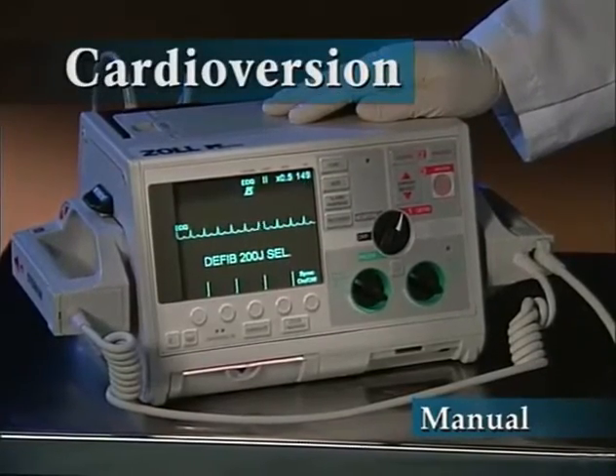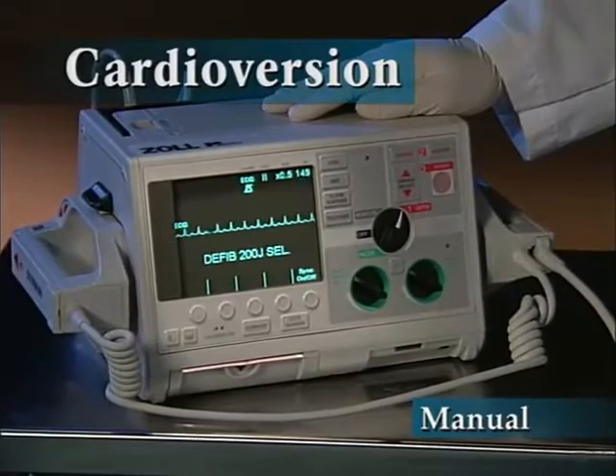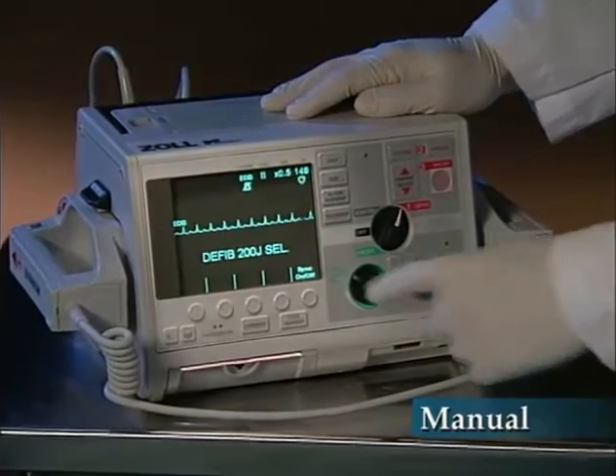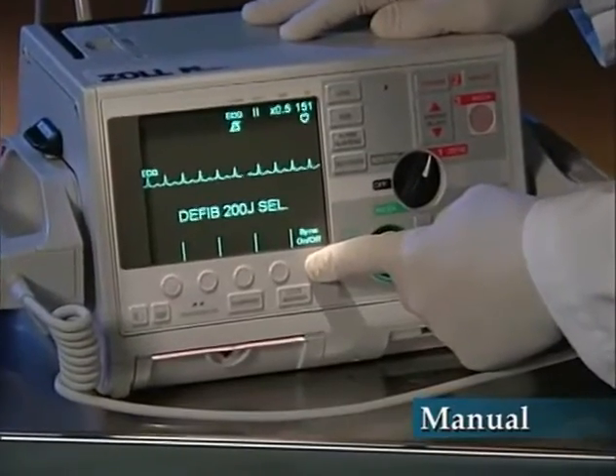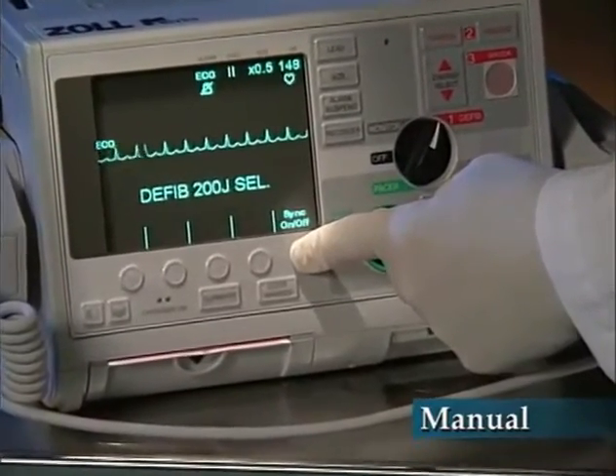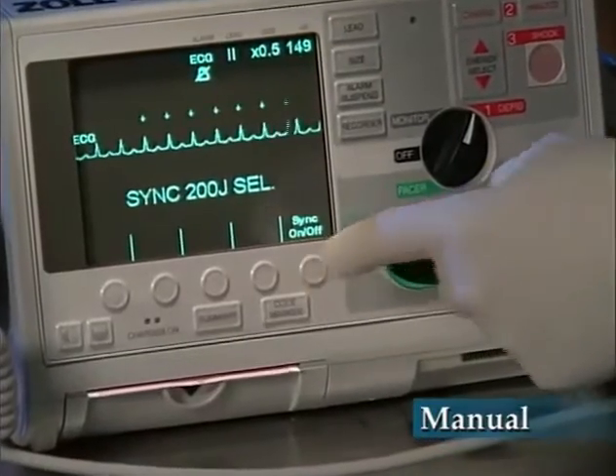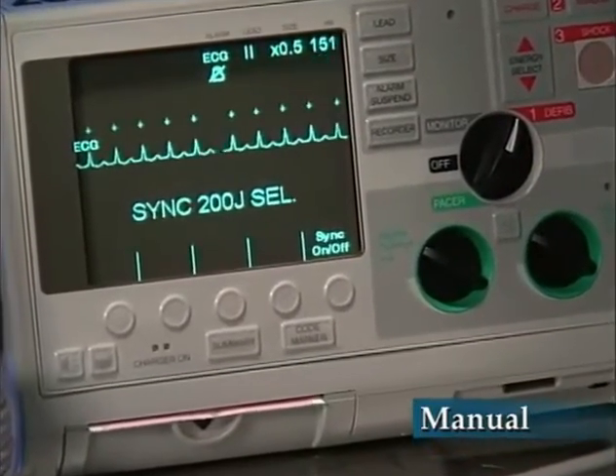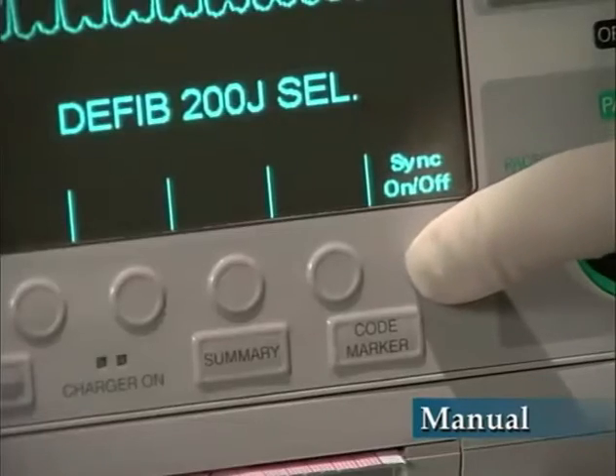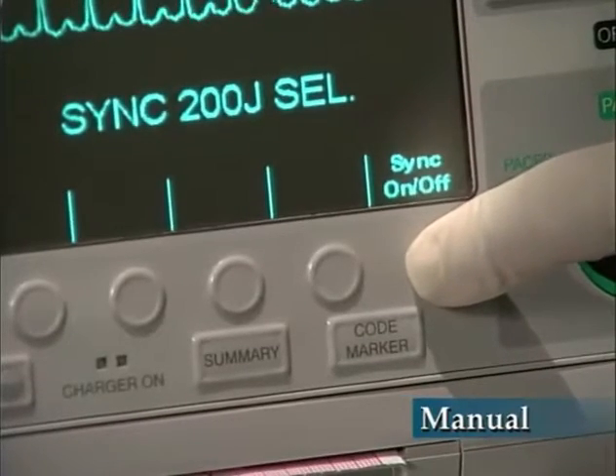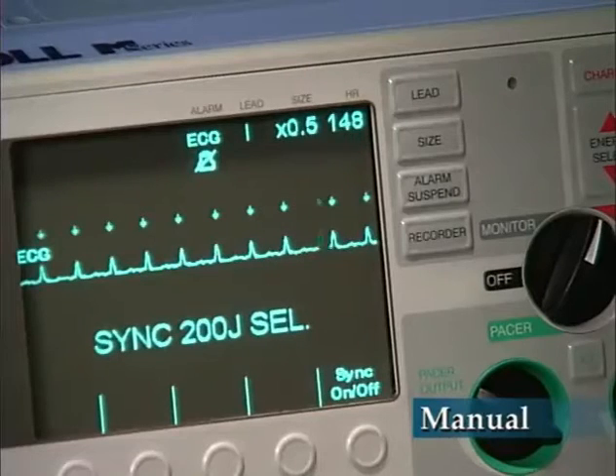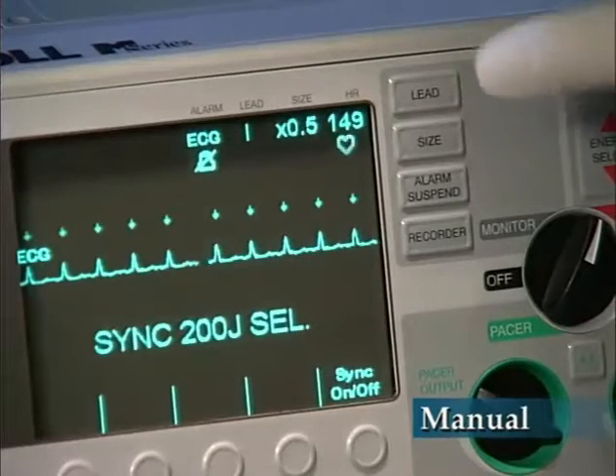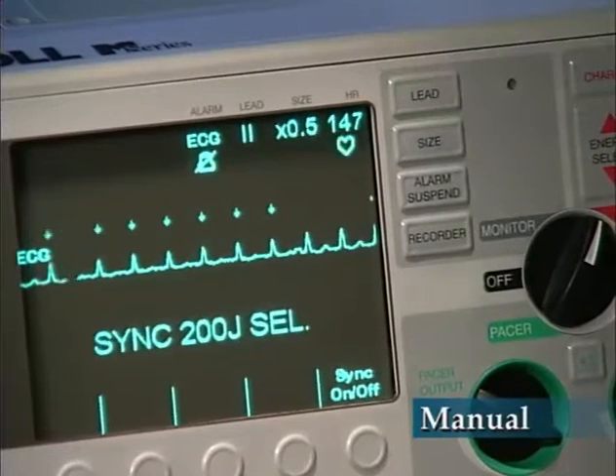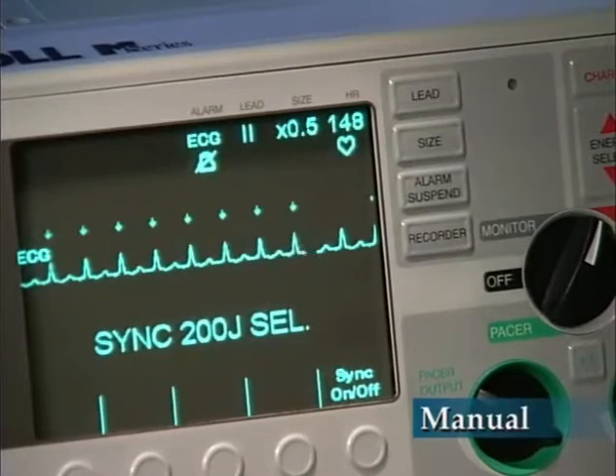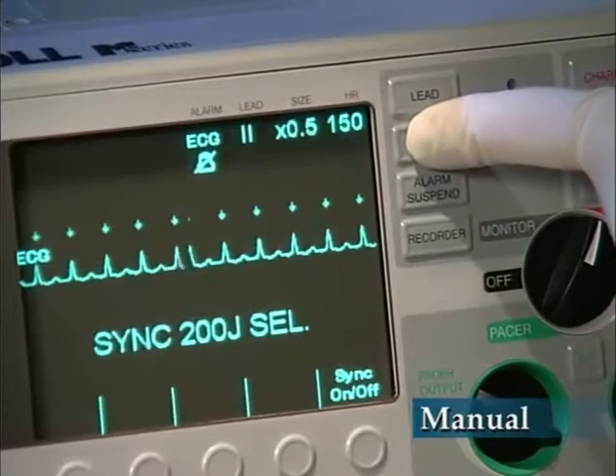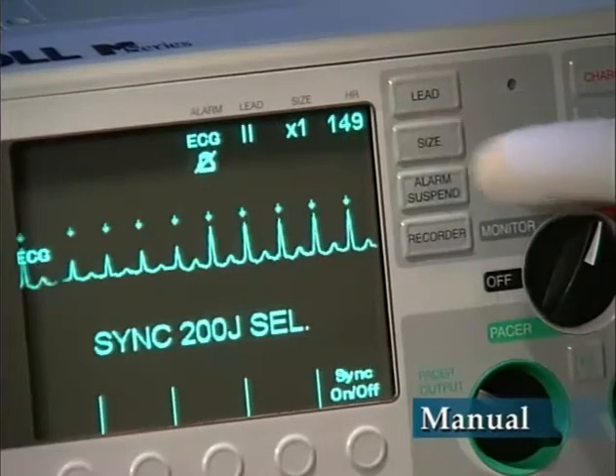When in the defib mode, synchronized cardioversion is available to synchronize discharge with the ECG R wave. The sync on-off is controlled by a soft key. ECG should be obtained via a patient cable, since it provides the best signal and lead selection. After pressing the soft key labeled sync, a marker will appear above each R wave to indicate where the discharge will occur. Verify the marker's location is appropriate and consistent with each beat. Use the lead and size button if necessary to establish consistent synchronization.